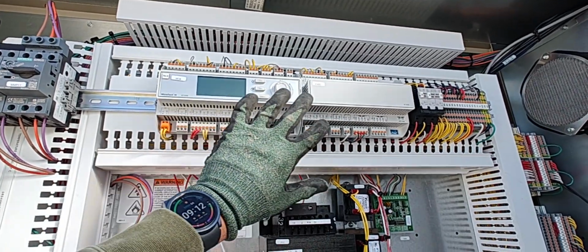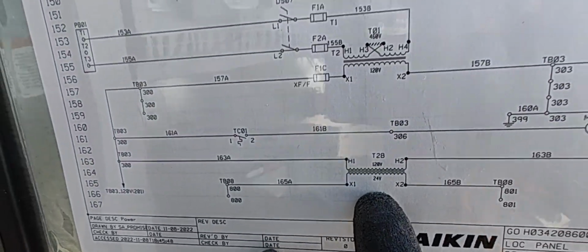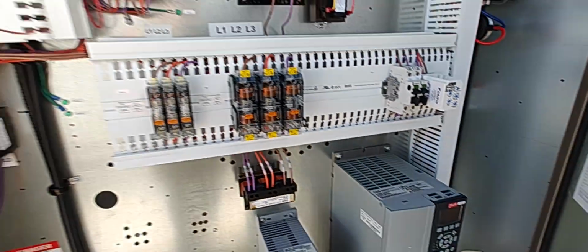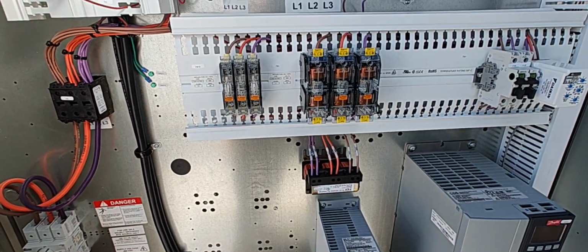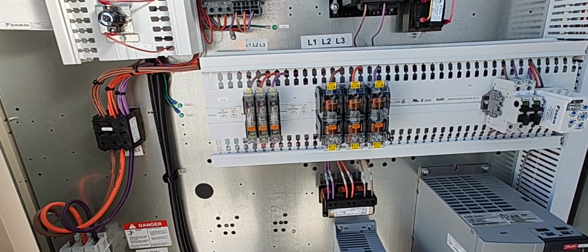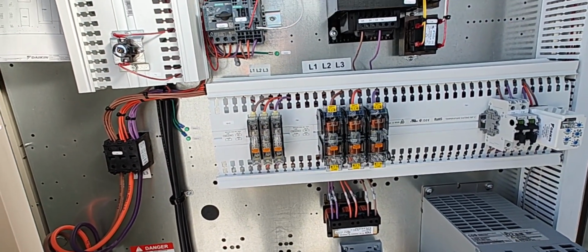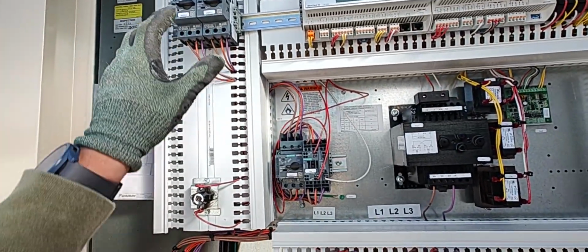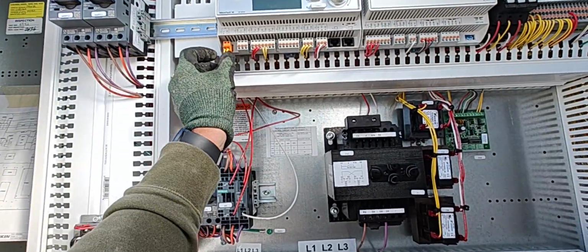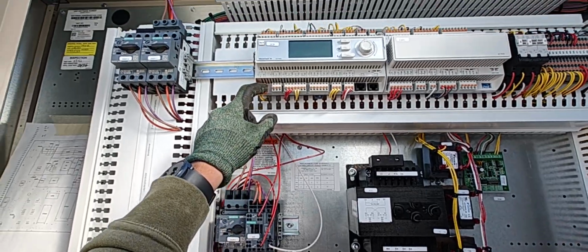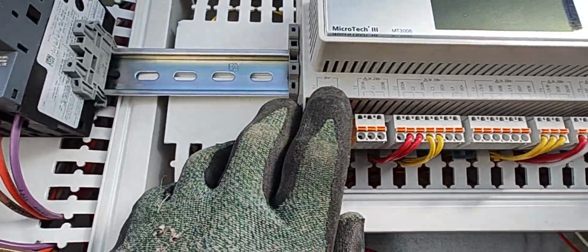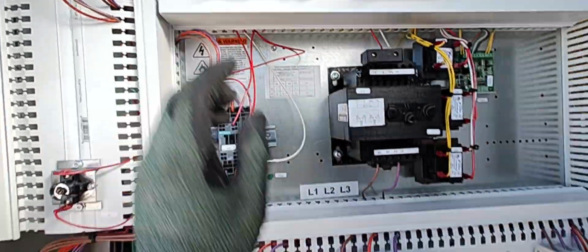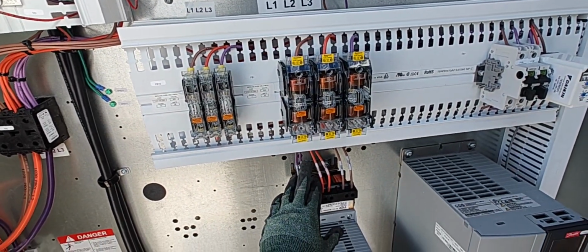And it's running some of this on 120, and then it's hitting a secondary transformer, 120 volts to 24 volts. So essentially that's in the field when you're going to see this kind of stuff, how to diagnose it. If I come and see this, I need to know what it is.